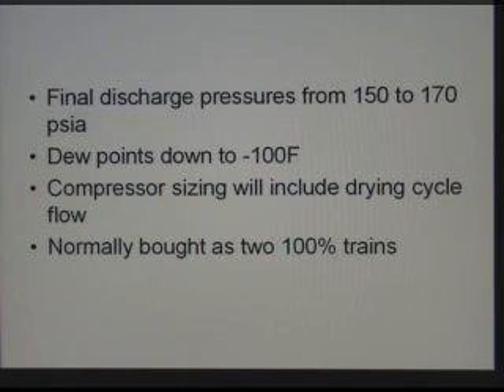And if the air consumption is such that it matches the one train capability, that means it's running all the time, where rates are pretty high, maintenance costs are going to be high. But it also means that if any other utility user comes on, you have to start the second backup machine to satisfy the needs of the extra air consumers, and so you no longer have any redundancy, and you no longer have any ability to swap back and forth or take a machine offline to do work on it while the other one picks up the load. So we always want to have about a 75% duty factor on these compressors.